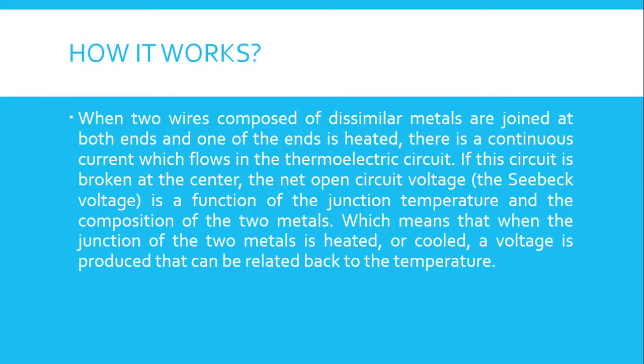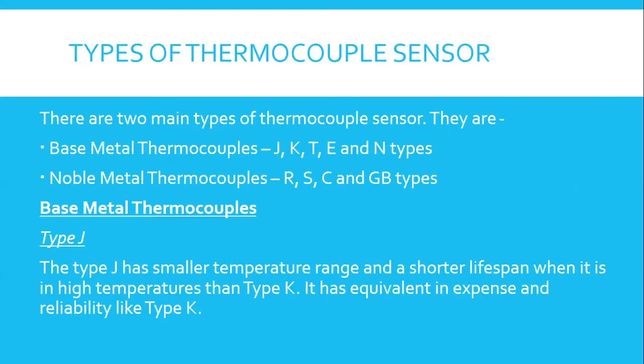How it works. When two wires composed of dissimilar metals are joined at both ends and one of the ends is heated, a continuous current flows in the thermoelectric circuit. If this circuit is broken at the center, the net open circuit voltage is a function of the junction temperature and the composition of the two metals, which means that when the junction of the two metals is heated or cooled, voltage is produced that can be related back to the temperature.